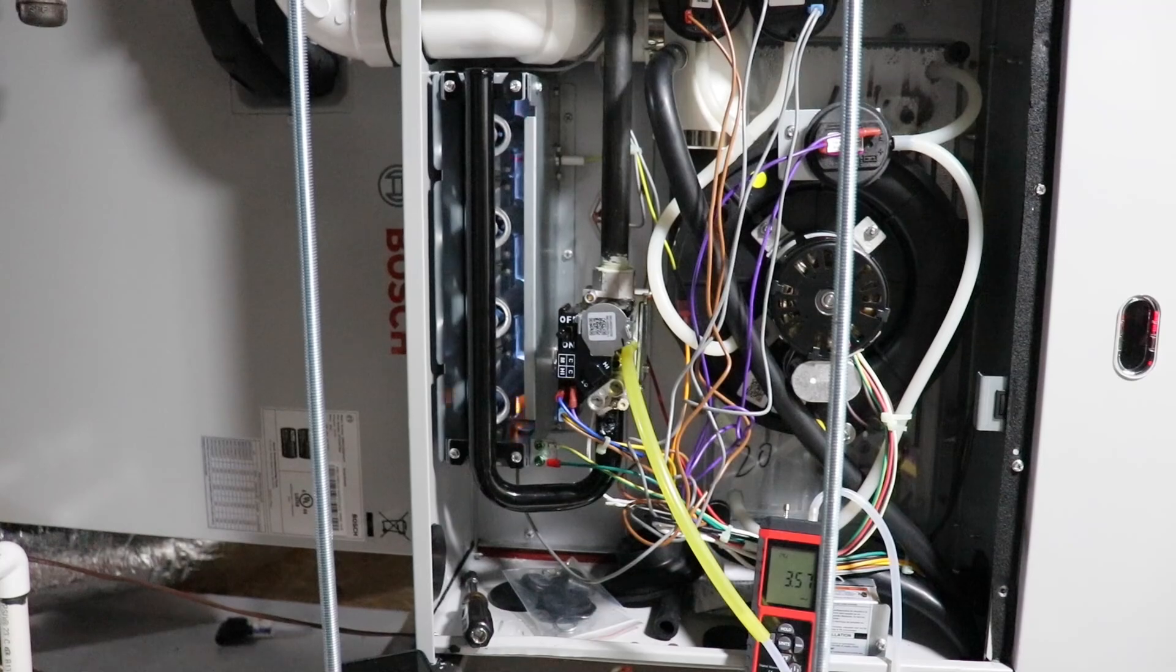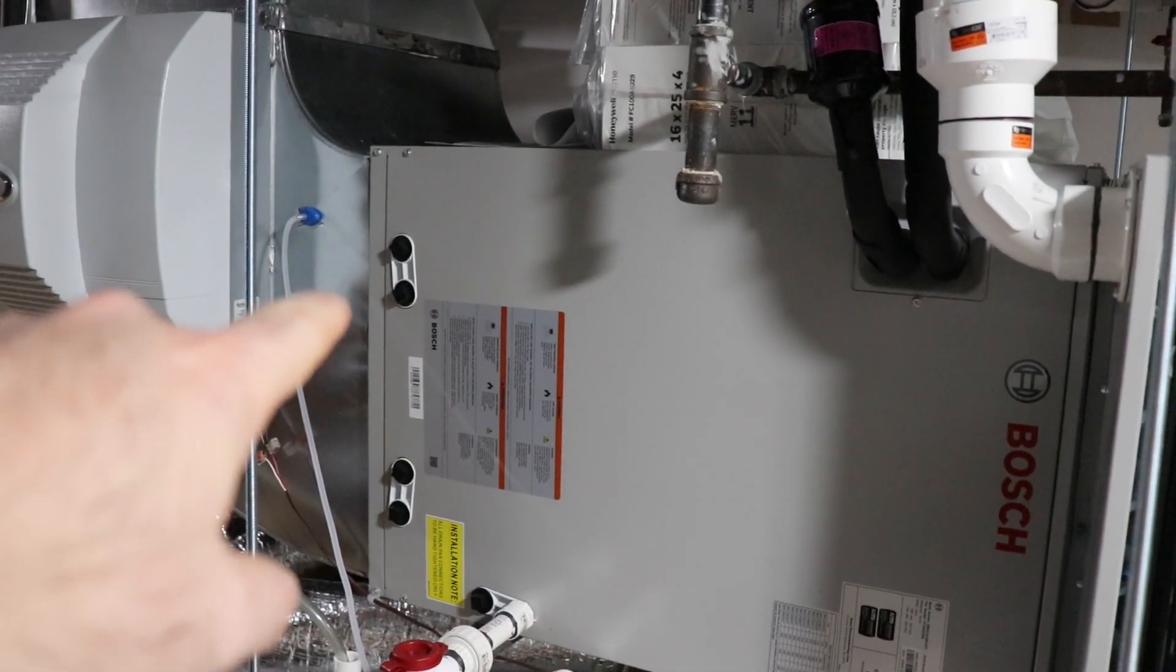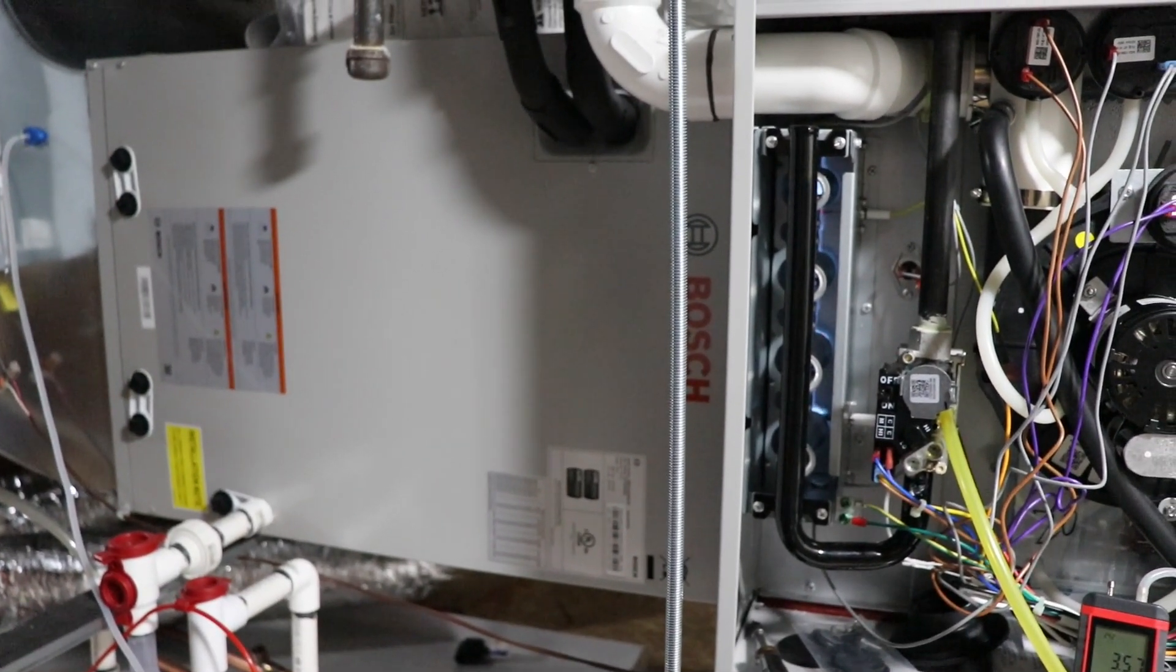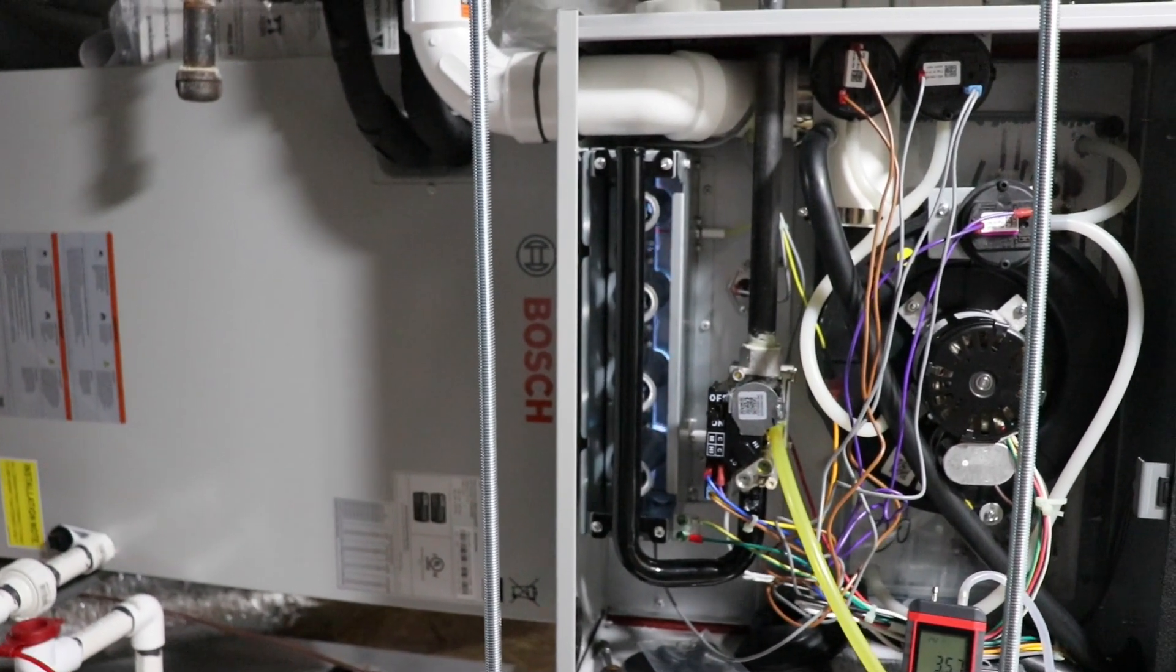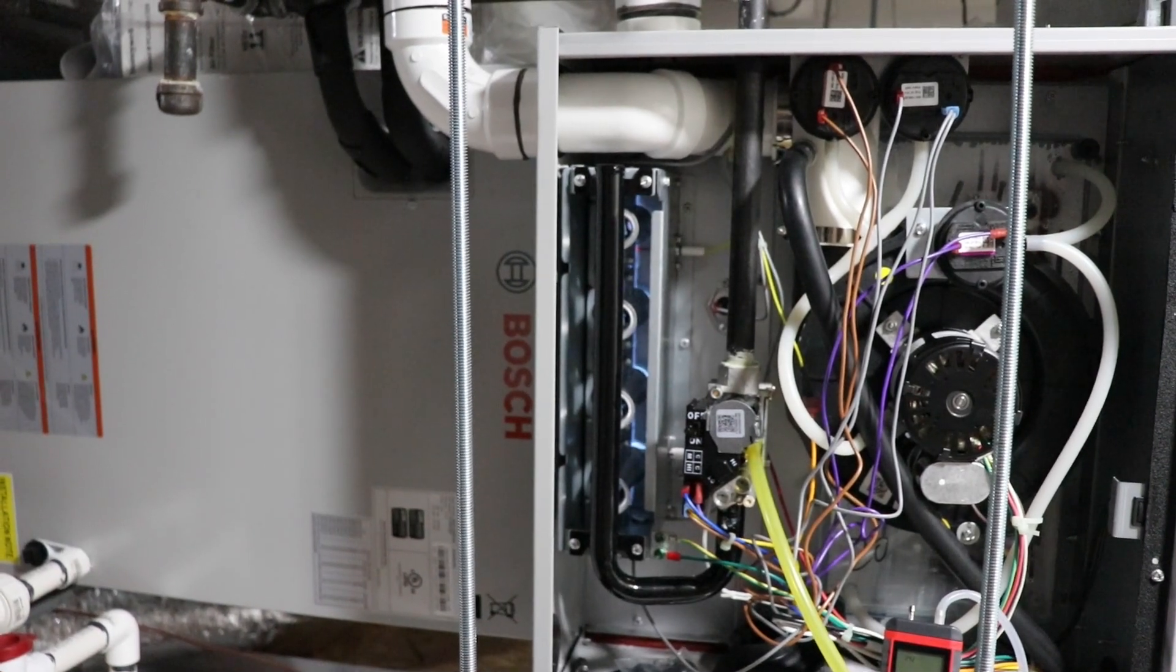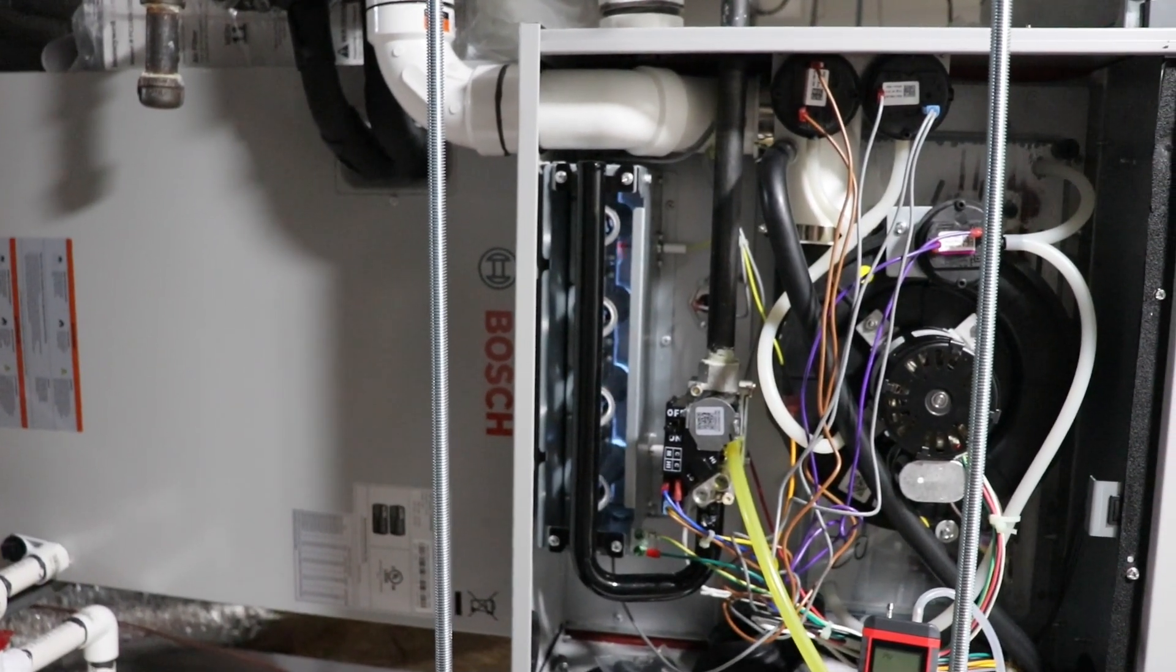As I've mentioned previously, but if you had the electric heat coils, they would be after the A-coil here, it would be over there somewhere. They could all be just different. But you would be getting the output of the compressor at whatever efficiency you're getting at cold temperatures, plus the one-for-one energy of the resistive heat going in. So you'd be getting two sources of heat still versus one.